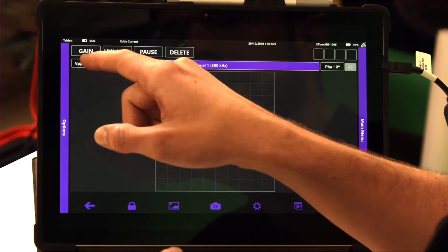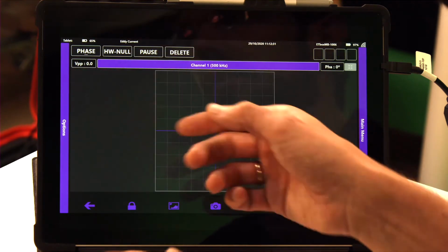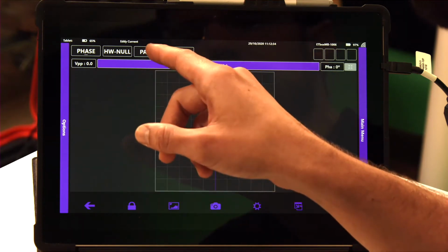In this case, as we're talking about eddy currents, we can manipulate the offset, the gain, or the phase, do a hardware null to center the signal, or pause the acquisition. As we see, an orange tag appears that indicates the acquisition is stopped.